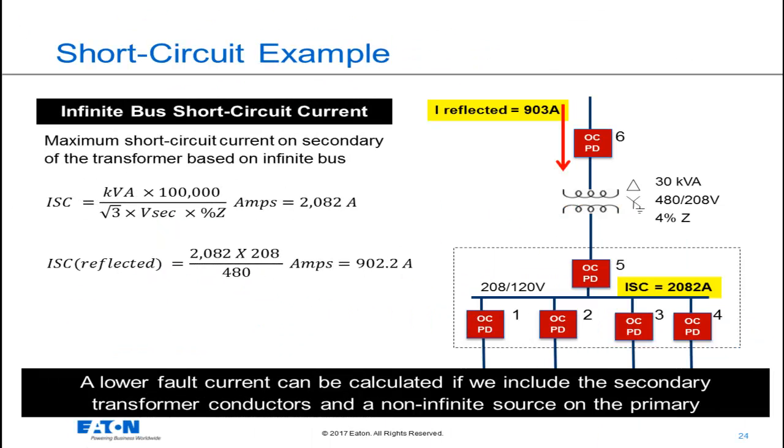Let's do a real-world example. I have a 30 kVA transformer with a 4% impedance. The maximum available short-circuit current that can be found on the secondary is 2082 amps, and it's calculated here on this slide. That current reflected to the primary is what the overcurrent protective device number six will see for a fault on the secondary, and that number is 903 amps. For circuit breaker applications, these are important parameters. Remember, this is based on a 30 kVA transformer with 4% impedance. If you change any of those two parameters, the numbers will be different.